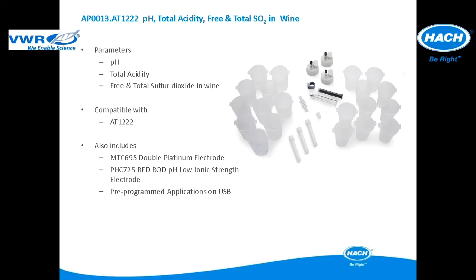This application package is used for pH, total acidity, and free and total sulfur dioxide in wine applications. The application package is compatible with the AT1222. It includes all of the items pictured and comes with a pHC725 red rod low ionic strength pH electrode and the MTC695 double platinum electrode for redox titrations. The pre-programmed applications are included in a USB application key.